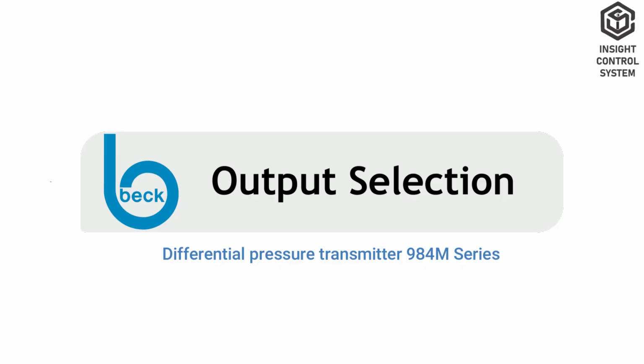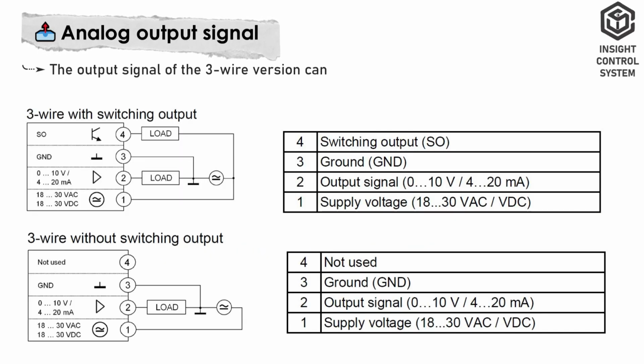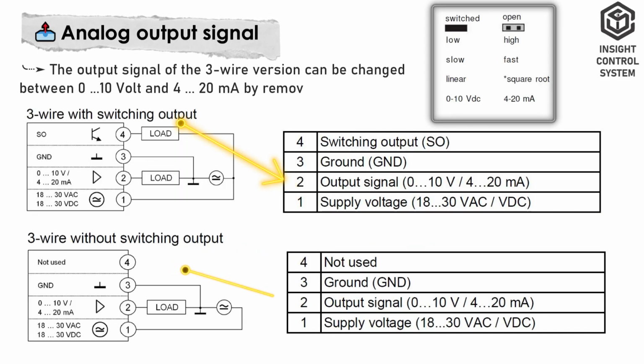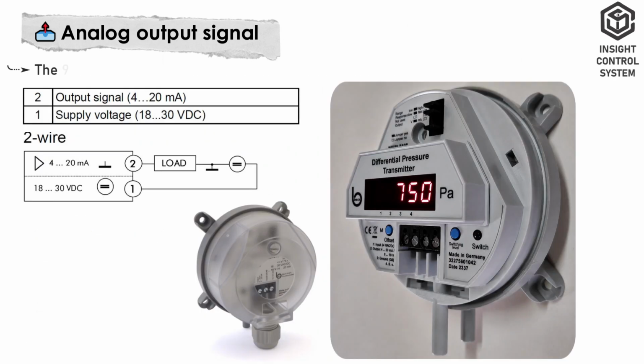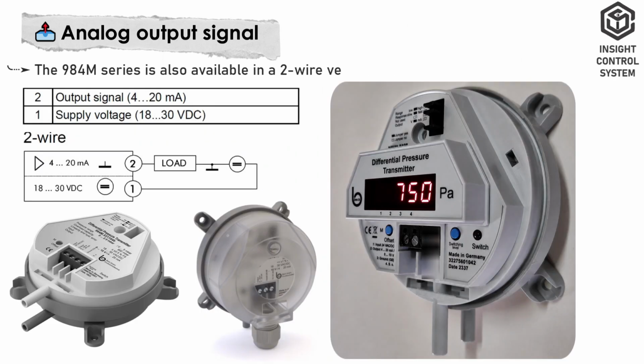Output selection. Analog output signal. The output signal of the 3-wire version can be selected between 0 to 10 volts or 4 to 20 milliamps by changing the jumper configuration. The 984M series is also available in a 2-wire version with a 4 to 20 milliampere output signal.